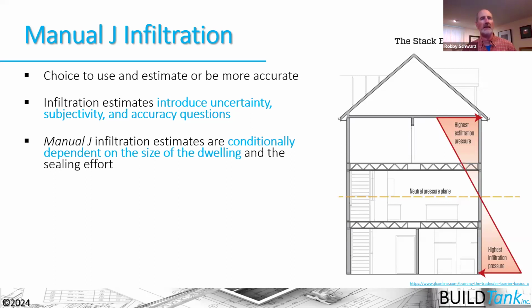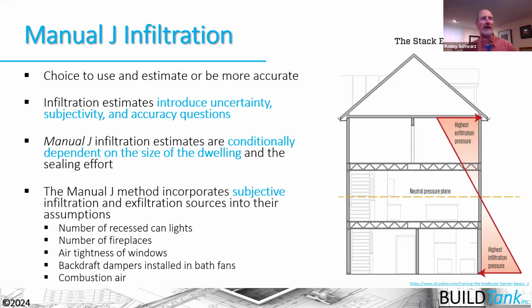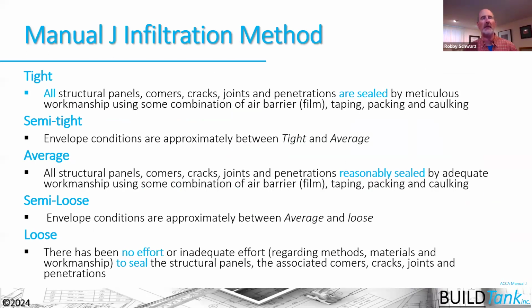The way that Manual J looks at the infiltration of the house is primarily from the perspective of stack effect, and it's dependent on the size of the dwelling there. So bigger volume dwellings, bigger square footage dwellings, they're going to assign greater stack effect or greater infiltration in that house there. So again, the Manual J method incorporates this pretty subjective infiltration and exfiltration sources that are based on some assumptions like the number of recessed cans, the number of fireplaces, the air tightness of windows, all these types of things that are added into our houses there. And so we want to try to be ultimately more accurate.